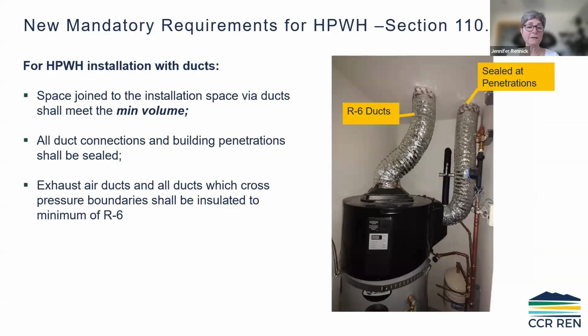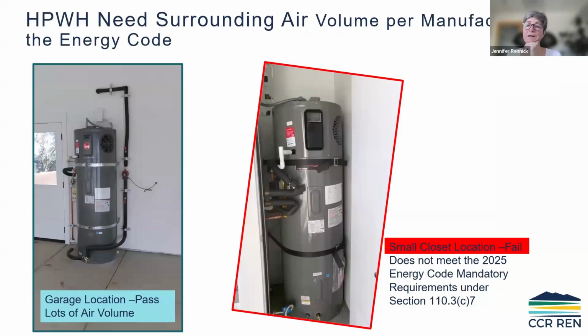And if you go with a ducted situation, the code says you can use ducts to connect to another space. Same idea, now your ducts are open to that other space. They could be connected to the outdoors, so then you have a vast volume of air to work with, or they could be connected to a different part of your house, and that could be included as the volume. And the new requirement is if the ducts do cross that pressure boundary, they need to be sealed and have R6 insulation.